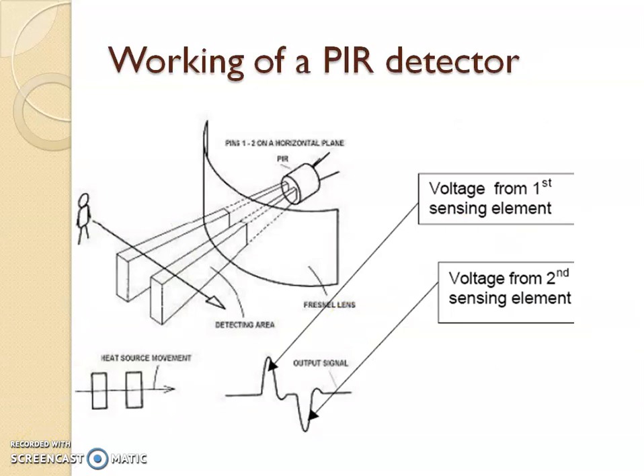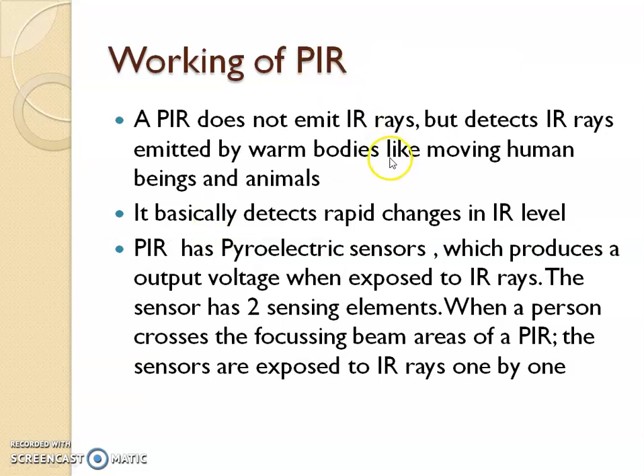The same PIR detector can also be installed horizontally. The device installed in a horizontal fashion will detect an intruder when he passes through the space. One important thing in PIR to note: it does not emit any infrared rays but only detects infrared rays. This is because infrared rays are detected from the warm bodies of human beings or animals moving through that area, as all living bodies generate infrared rays which are sensed by the PIR.